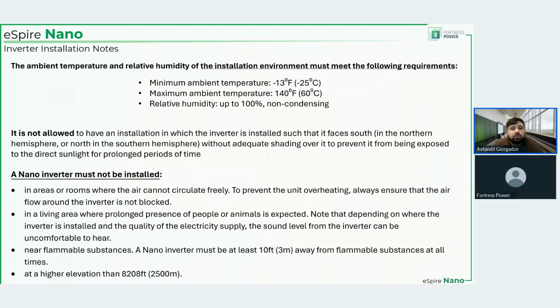Next, one must be very careful while selecting the environment in which the inverter will be installed, and one of the first things to pay attention to is the ambient temperature. The minimum ambient temperature for the inverter is minus 13 degrees Fahrenheit, and the maximum ambient temperature is 140 degrees Fahrenheit. Relative humidity is up to 100%, but non-condensing. You'll notice I'm not mentioning batteries here. They have a slightly wider temperature range due to the HVAC that we have in place.